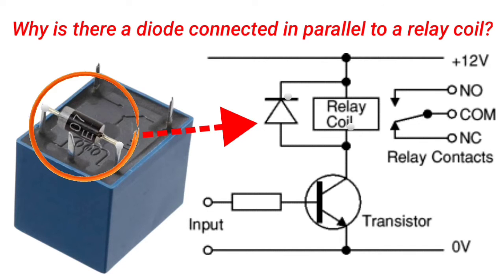This voltage is generated in the coil when the current flow is interrupted. The purpose of the diode is to allow the current flowing through the coil to continue circulating when the relay is deactivated.